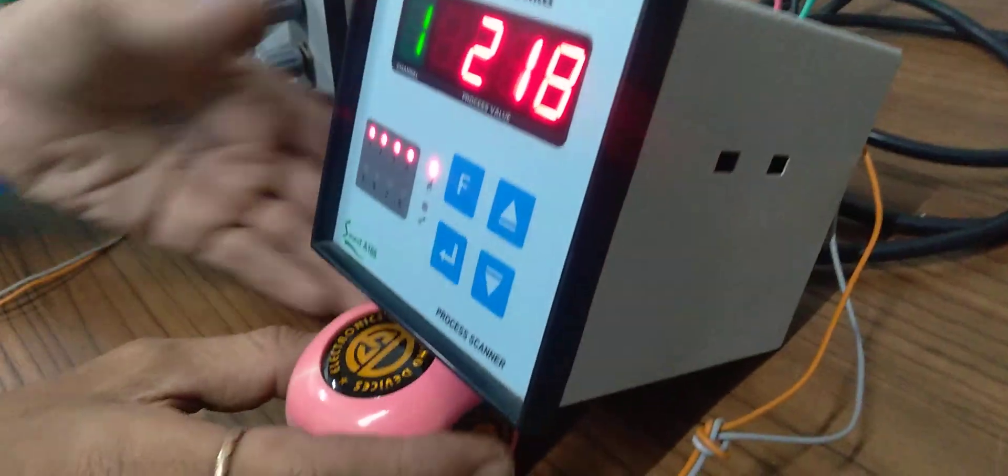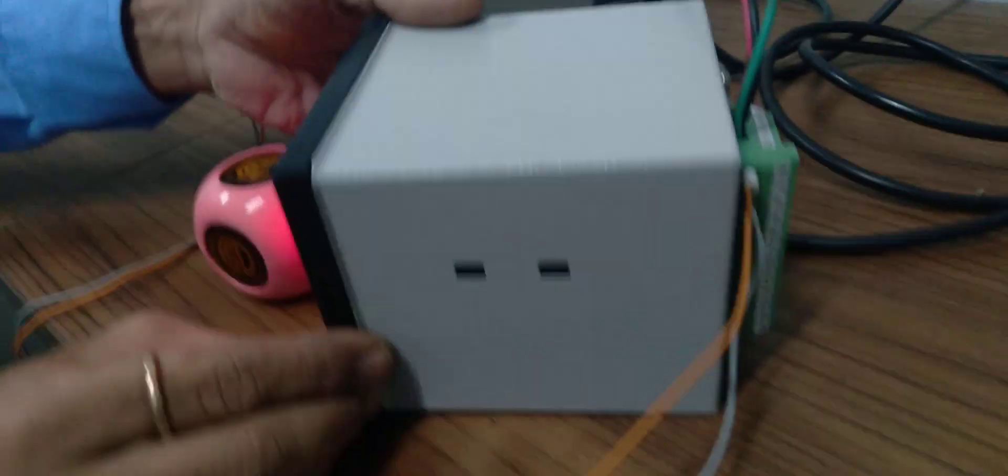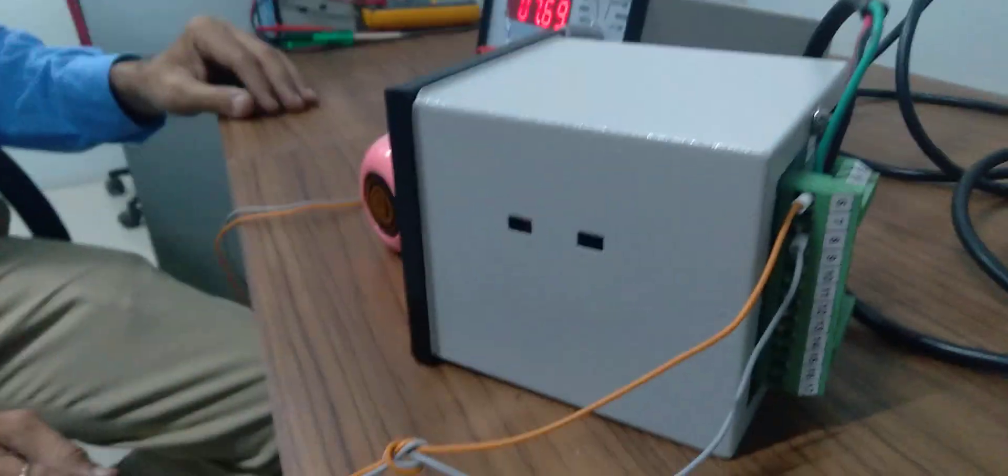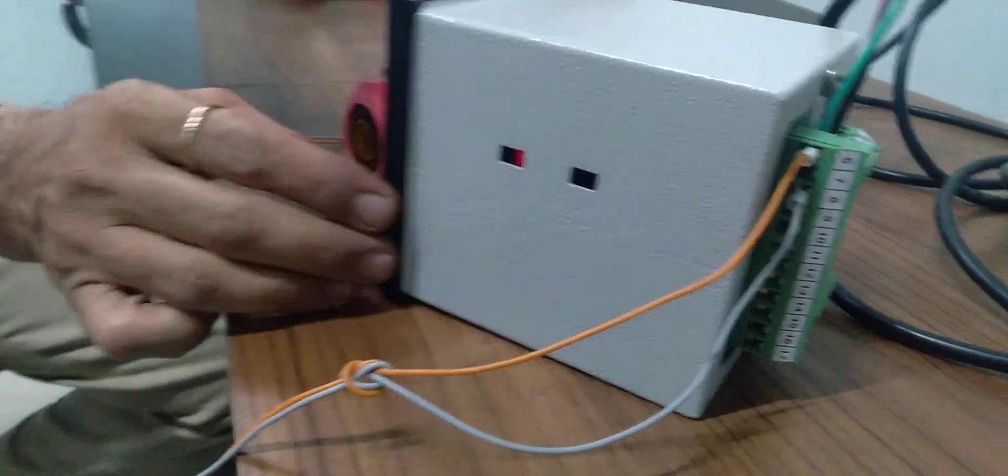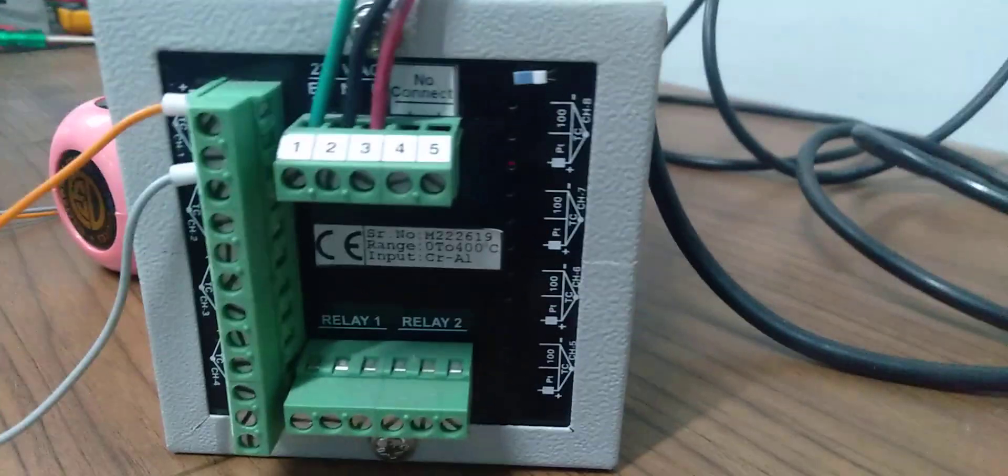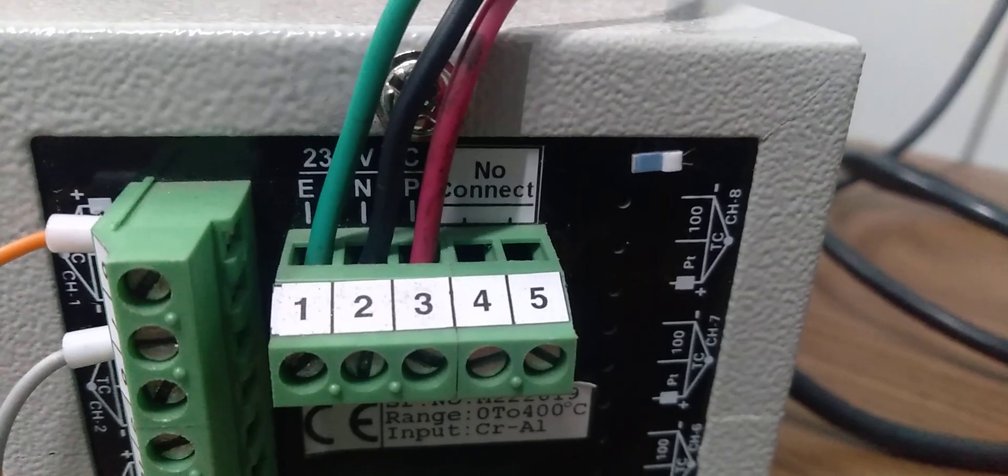At the back of the instrument is the back card. This is a four-channel card where the four channels are connected. The power supply is connected here, 230 volts AC. These two are the relay outputs, relay 1 and relay 2.